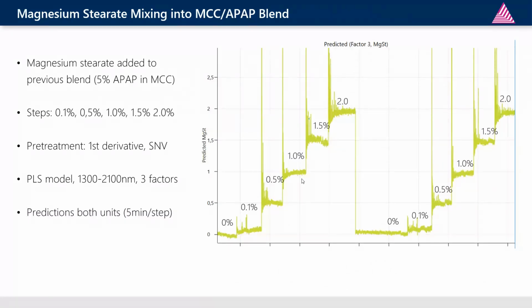Then we tested the magnesium stearate addition. Actually, I must correct: this is magnesium stearate in MCC, in the blend we did before. And these are the data from both instruments which were also used to create the method. You see here also the blending effects. Every step here is just the addition of magnesium stearate into the blend, and you can actually see the blend curve in the feed frame and some spikes, like lumps, in the beginning before the blending is really done. You can also see that both instruments are behaving very similarly to each other. They both see the same spikes. More or less, both instruments were 120 degrees away from each other on the feed frame. Yeah, that was what I wanted to show you about these trials we were running.